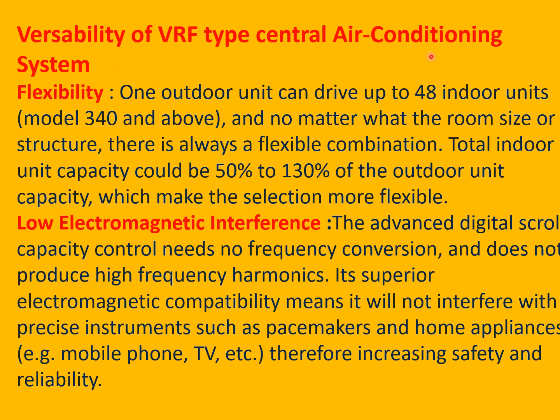Friends, the VRF type systems are very versatile. They have the flexibility that one outdoor unit can drive up to 48 indoor units, and no matter what the room size or structure, there is always a flexible combination. Total indoor unit capacity could be 50% to 130% of the outdoor capacity, which makes selection more flexible. Low magnetic interference. They have advanced digital capacity control, need no frequency conversion and do not produce high frequency harmonics. Their superior electromagnetic compatibility means they will not interfere with precise instruments such as pacemakers and home appliances.